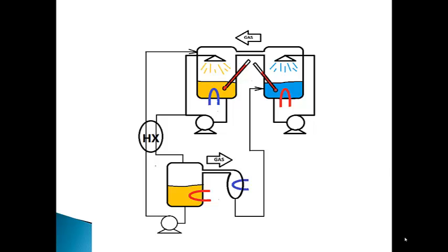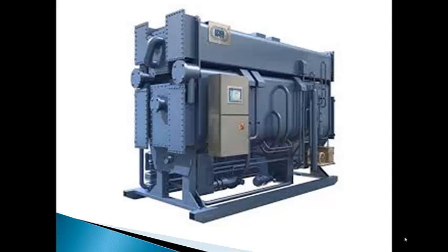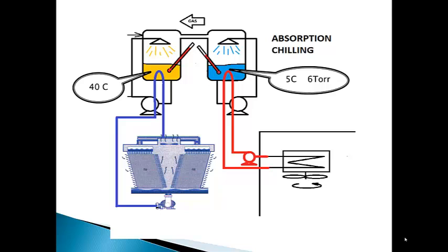Those skilled in the art of heat pumps will recognize this as an absorption chiller. It was invented 150 years ago in France and is now in service all over the world, providing air conditioning in large buildings. Lithium bromide is the most commonly used salt in the brine. The evaporator typically operates at an absolute pressure of 6 torr and a temperature of 5 degrees Celsius. The evaporator is the sink for the air conditioning load.